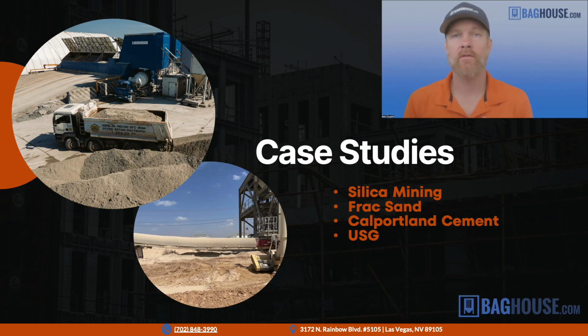Things have been moved and changed over time. The systems are totally out of balance. Sometimes the dust collector is undersized or oversized or not properly configured. So that's basically a blueprint that we can then hand the customer to say, if you want to address the dust emission sources that you could see, if you want to make sure your exposure limit requirement is met, and if you want to follow the best practice to make sure that you have dust collection under control at your site, here's your blueprint for what to do, a step-by-step checklist, and then we go to work implementing that.